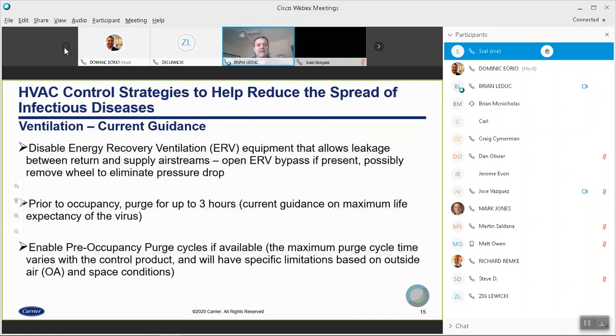They recommend disabling ERV systems if they're present, which could possibly have leakage between the supply and return airstreams, even to go so far as to remove the wheel if possible. I question whether or not that would be a viable strategy, but at a minimum, if there's a bypass present, they recommend opening it and bypassing air across the ERV. There are some other concerns about that I'll get to later on, but this is again the ASHRAE guidance.